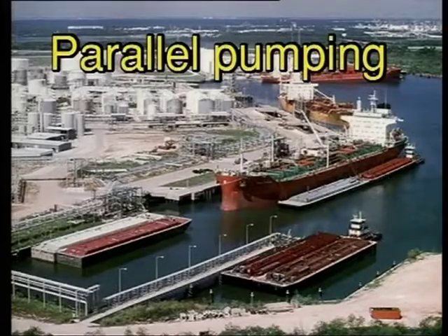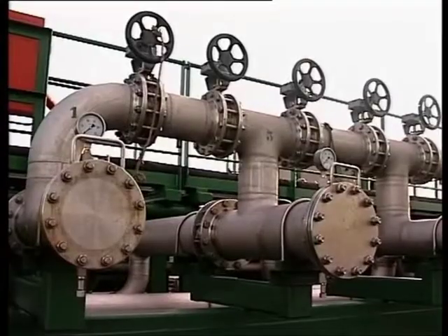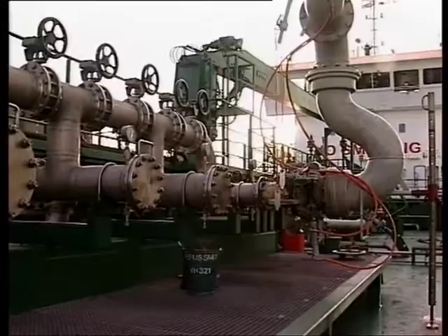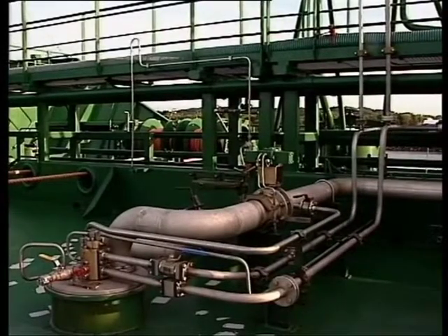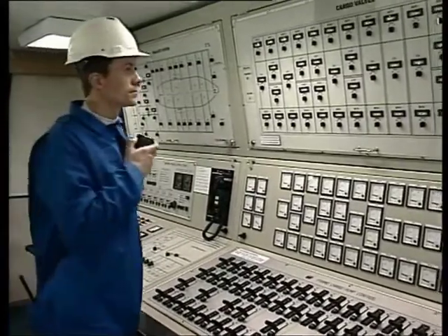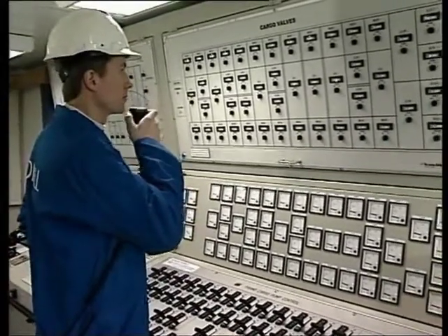Discharging of homogenous cargoes — parallel pumping. Running centrifugal pumps in parallel is, for example, when discharging the same type of cargo with a number of cargo pumps through a common shoreline. With Framo cargo pumps, this is easy as the Framo system gives the operator maximum flexibility and stepless speed and capacity control of each individual cargo pump.